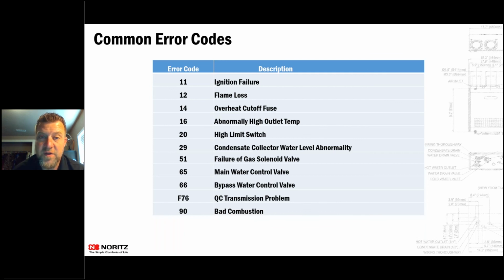If you do get a 73 code, it just means that you flipped dip switches with the unit plugged in. All you have to do to reset that is unplug the unit and plug it back in. Same thing with any error code on one of our units: you can clear it by unplugging the unit, waiting 15 to 20 seconds, and then plugging it back in.